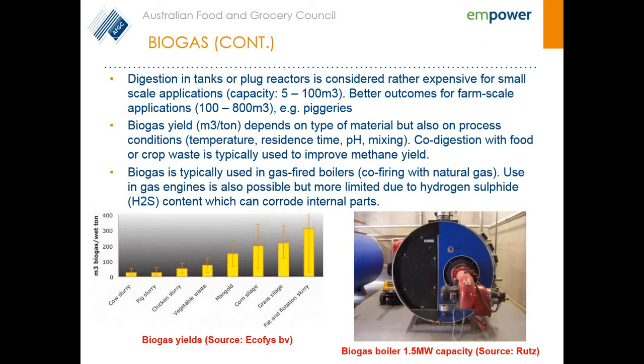The biogas yield depends on, apart from the type of material being fed into the system, certain process parameters such as temperature, residence times, pH, and the amount of mixing. When designing an anaerobic digestion process, these parameters will have to be evaluated to ensure you're getting the most biogas possible.